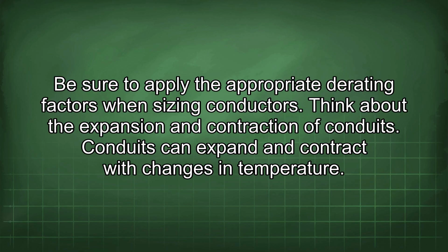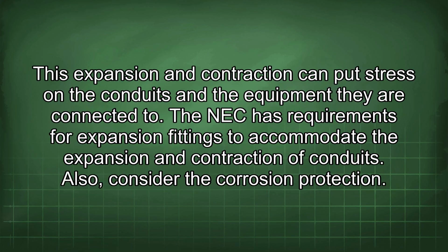Think about the expansion and contraction of conduits. Conduits can expand and contract with changes in temperature. This expansion and contraction can put stress on the conduits and the equipment they are connected to. The NEC has requirements for expansion fittings to accommodate the expansion and contraction of conduits.